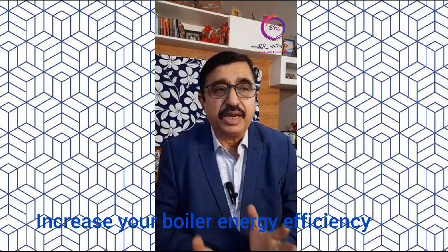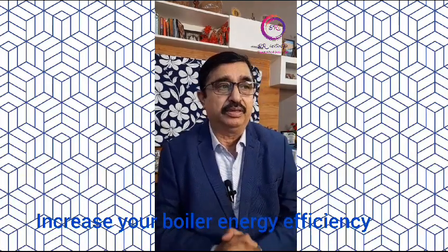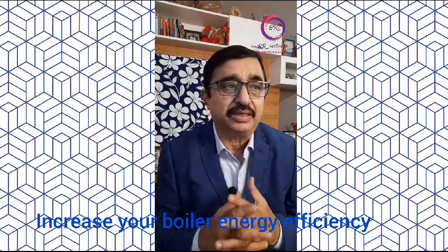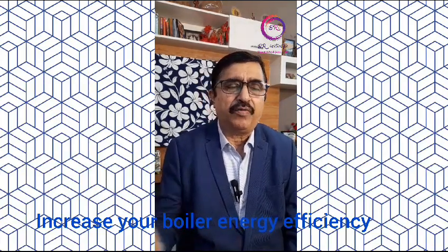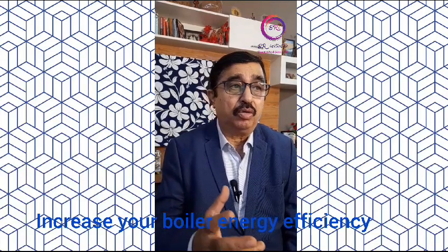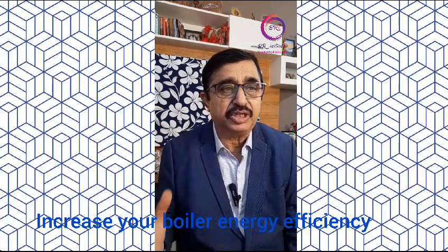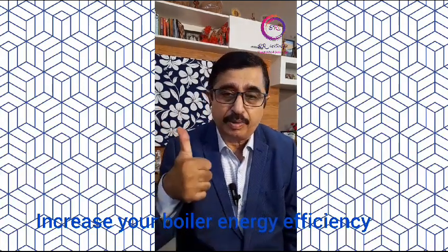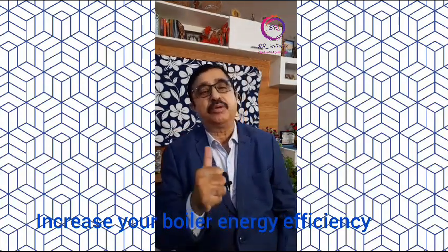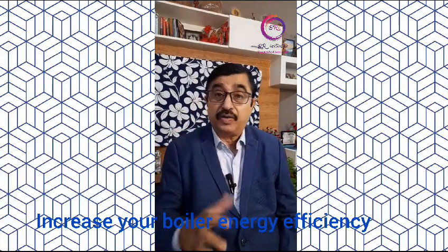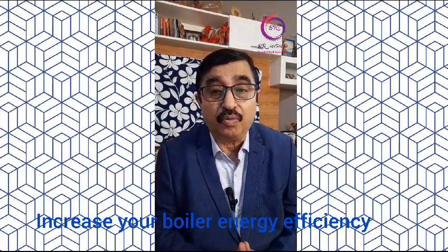Corrective actions must be taken by implementing cleaner technologies, fuel switching, and high efficiency burners, etc. Performance of the boilers basically depends on efficiency and evaporation ratio. Both of the above parameters slowly come down or diminish with time due to improper combustion, fouling of the heat transfer area, and poor operation and maintenance practices. Other factors also deteriorate the fuel quality and the boiler water quality.